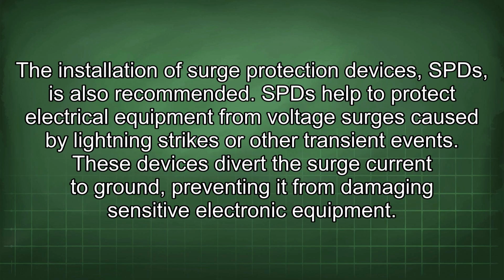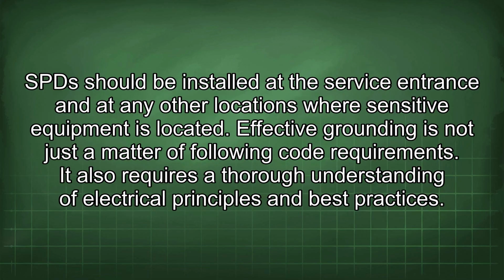The installation of surge protection devices, SPDs, is also recommended. SPDs help to protect electrical equipment from voltage surges caused by lightning strikes or other transient events. These devices divert the surge current to ground, preventing it from damaging sensitive electronic equipment. SPDs should be installed at the service entrance and at any other locations where sensitive equipment is located.